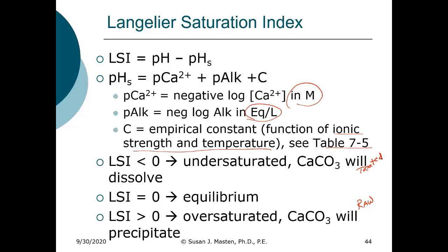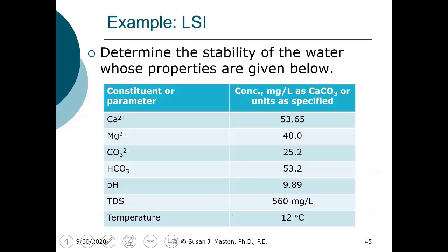So you have a water where treatment has shifted the equilibrium from oversaturation to undersaturation, and that would have potentially dissolved the calcium carbonate that would have been on the inside of pipes that provided this protective coating. That's something you almost never hear about, but it's something that actually did occur. And it really was a function of the treatment. The Flint River water itself was oversaturated. So let's look at an example.